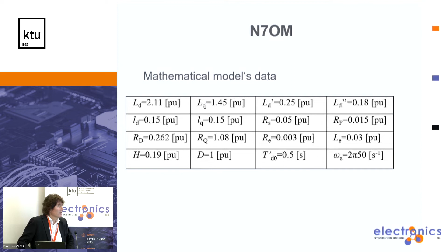And here are results. So for small changes, if we make a small step change of mechanical torque of 5% PU, we obtained almost identical results. You can see black - red is measurement, and black are results from the nonlinear model. So it means that the simplification by derivation of the model and not absolutely accurate measurement of parameters of the machine are small enough that the results are very good.